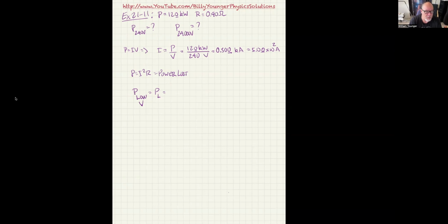So when I do the power loss due to the low voltage, that's I squared R, then the current going out is the 500 amps, and that's got to be squared times 0.40 ohms, and 500 squared times 0.4. That gives me 100,000 watts. So it's basically 100,000 watts.